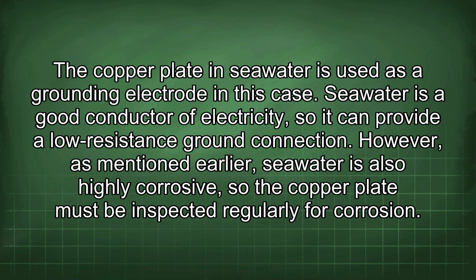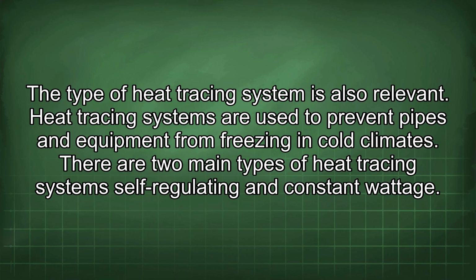The copper plate in seawater is used as a grounding electrode in this case. Seawater is a good conductor of electricity, so it can provide a low resistance ground connection. However, as mentioned earlier, seawater is also highly corrosive, so the copper plate must be inspected regularly for corrosion. The type of heat tracing system is also relevant. Heat tracing systems are used to prevent pipes and equipment from freezing in cold climates. There are two main types of heat tracing systems: self-regulating and constant wattage.